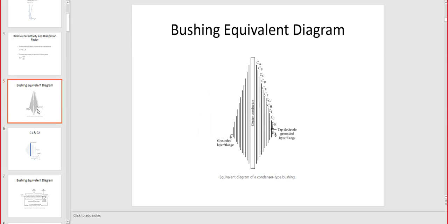Next slide is a bushing equivalent diagram. So any bushing can be seen theoretically as something that is made up of a series of capacitors in between the skirts of the bushing, and then in the middle you have the actual center conductor going from the transformer, connected to the windings, up to the top, where you have the lug connection for the cabling that is coming to the transformer. In between you have a ground flange, because the actual bushings go through the tank and come from the windings up to the transformer in the air where the cable will be connected. On the bushing there is a little bit of stress happening at that point because the electrical field gradient over there is 0, right? The tank is connected to the ground.